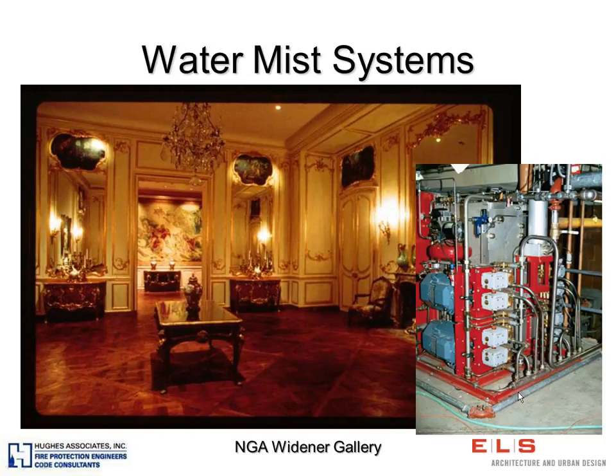So you have a big space requirement for a water mist system, just not in the area with the character-defining features. It's going to be located in some other location. Each water mist system has to be designed separately. It's all performance-based, meaning the code, the standard for water mist systems, doesn't say you shall put this many nozzles, you shall space them like this, they shall have such and such a density. So it's all performance-based, which is part of what makes the installation and the design costly for a system. They have big space requirements, but they also have very, very little water damage should you have a fire, because the droplets are so small and under such high pressure.